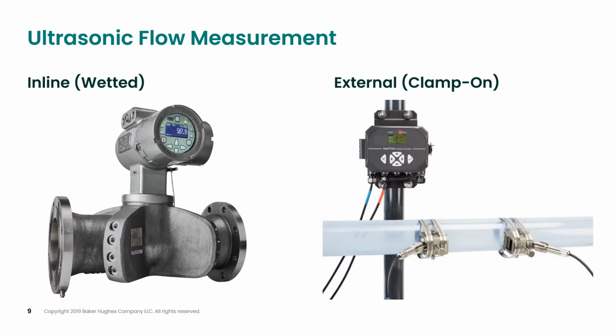With the transit time ultrasonic flow meter, the final meter can either be inline or wetted, or external or clamped on. With an inline meter, the transducer or transducer system is touching the process fluid. I use the term transducer system here since sometimes the actual transducer itself does not touch the process, but uses a buffer or other material that separates the transducer from the process. The transducer simply transmits the signal through this buffer into the process fluid. With an inline meter, the system is typically provided with a meter body or spool piece, and they are typically more accurate than an external or clamp-on meter.